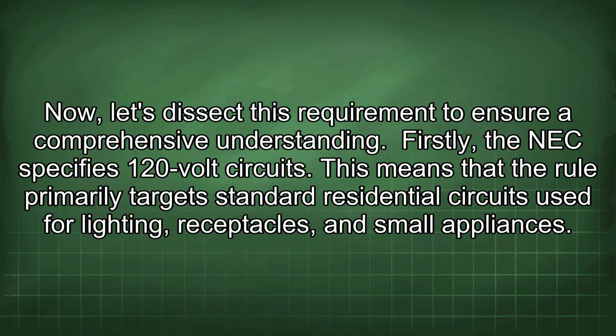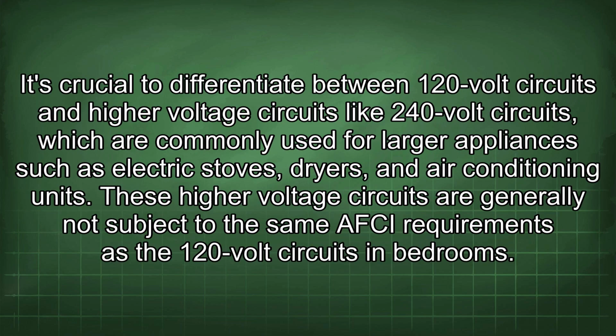Firstly, the NEC specifies 120-volt circuits. This means that the rule primarily targets standard residential circuits used for lighting, receptacles, and small appliances. It's crucial to differentiate between 120-volt circuits and higher voltage circuits like 240-volt circuits, which are commonly used for larger appliances such as electric stoves, dryers, and air conditioning units. These higher voltage circuits are generally not subject to the same AFCI requirements as the 120-volt circuits in bedrooms.